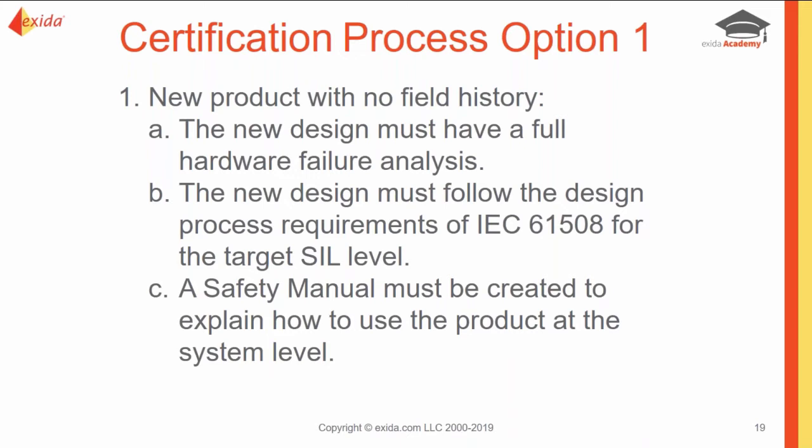For this, first of all, your new design has to have a full hardware failure analysis done. What was that hardware analysis? That is your FMEDA, your failure mode effect and diagnostic analysis. That's going to give you your failure rates. That's going to cover that random integrity or that circle for that probability of failure.